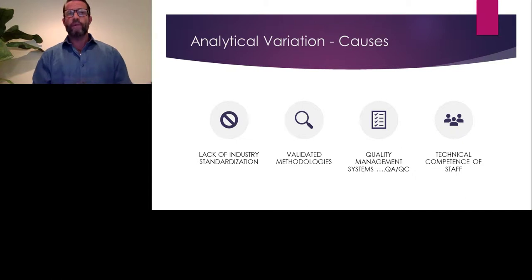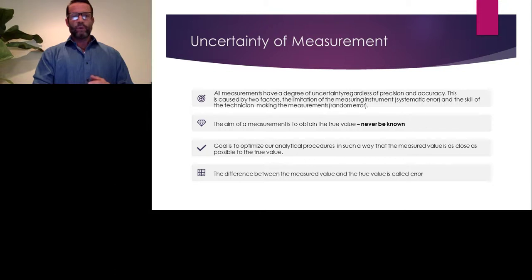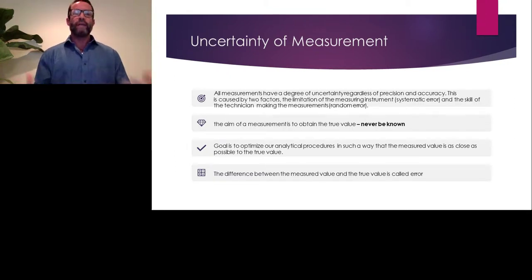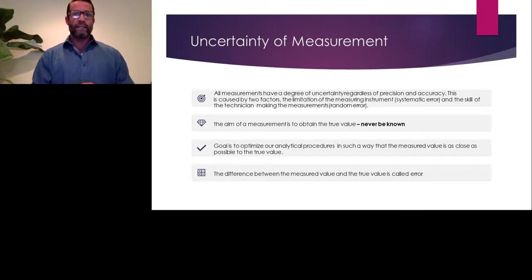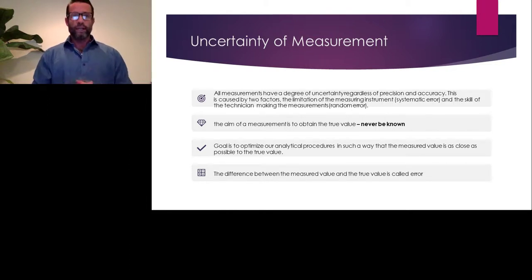We also have the technical competence and qualifications of staff. And one of the most important topics I want to dive into is what we call the uncertainty of measurement. This is part of analytical variation — we have an uncertainty of measurement, and within a lab we call that our uncertainty budget. All measurements have an uncertainty regardless of the precision or accuracy of the measurement. There are very few true measurements; they must be traceable back to NIST. The difference between the measured value and the true value is what we call error, or bias.